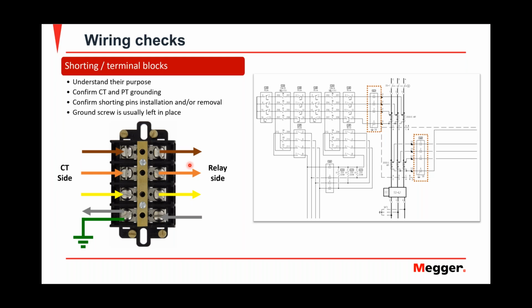So the relays show voltage. So everybody assumed, oh, the relays must be fine. But all these shorting pins were left inside. So the relay was not seeing currents. So that transformer blew up and it went on fire because somebody forgot to pull these shorting pins. Maybe they did not understand how it worked, but we're going to go through it.